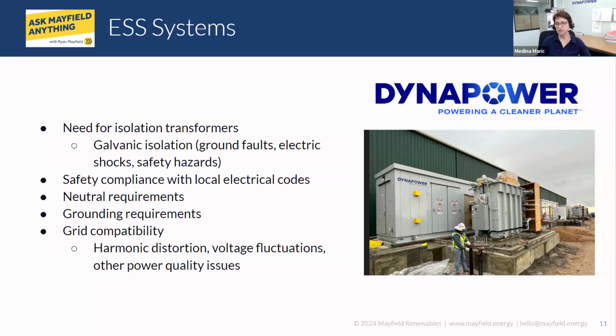Yes, on energy storage inverters that can come back if the ground loop is closed, and there is a lot of fluctuating currents that can come back. That can create a lot of problems with sensitive electronics and controls, and we have experienced that firsthand. Okay, so within the energy storage inverter itself, yes, seeing those coming back to it is causing problems, and then either creating whatever issues, shutting down or anything like that.